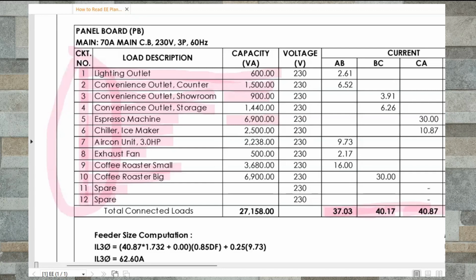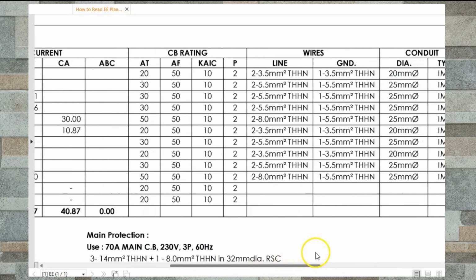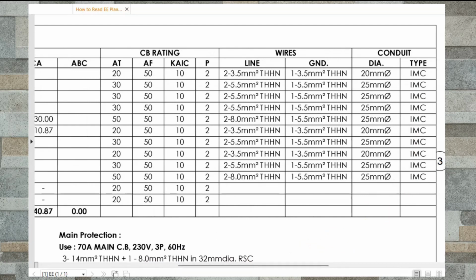And then bawat branch ng circuit is merong corresponding circuit breaker. So tingnan natin to. If sa circuit 1 natin, meron tayong 20 ampere na circuit breaker. Yung wire niya is dalawang 3.5. Yung ground isang 3.5. Saka 20 mm diameter na IMC. Ibig sabihin naka-expose yung ating mga conduit. So and then 30 amperes for circuit number 2, number 3, number 4, number 5, number 6 is 20, number 7 is 30, number 8, 20, number 9, 30, number 10, 50, 11 is 20 amperes, 12 is 20 amperes circuit breaker. So if yung breaker mo is 20 amperes, yung wire is 3.5.